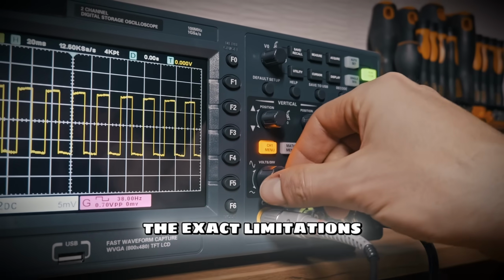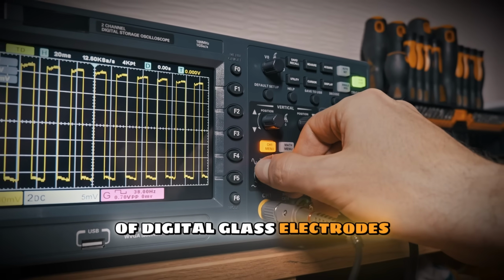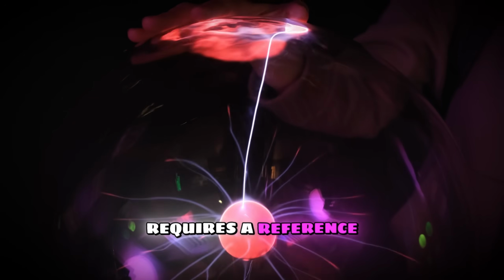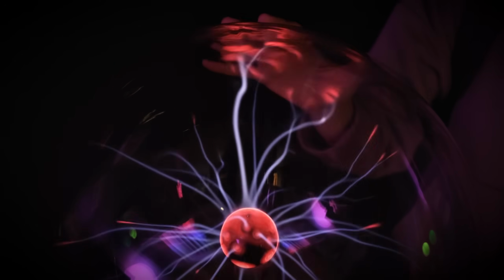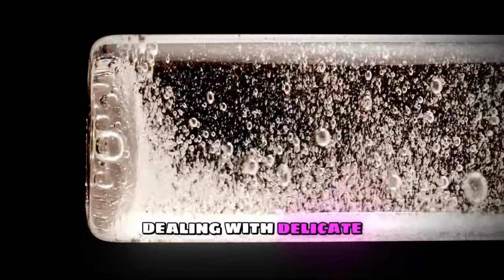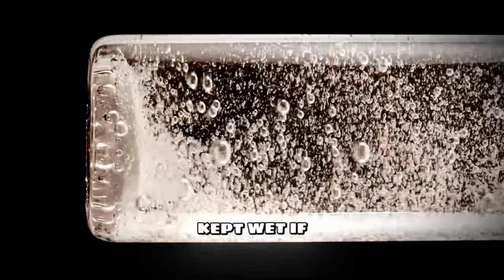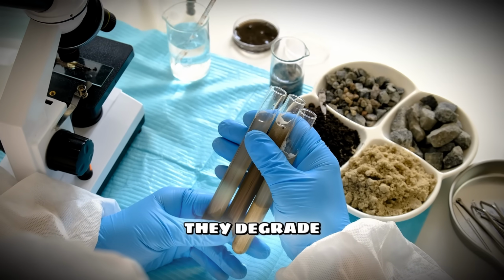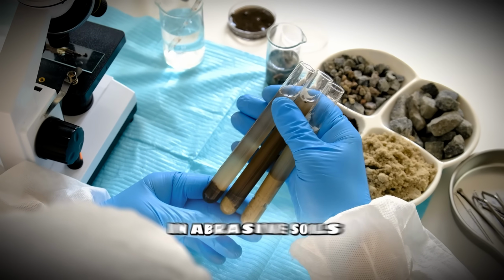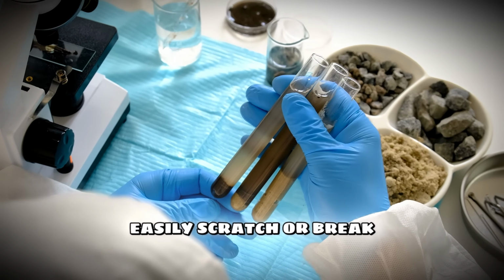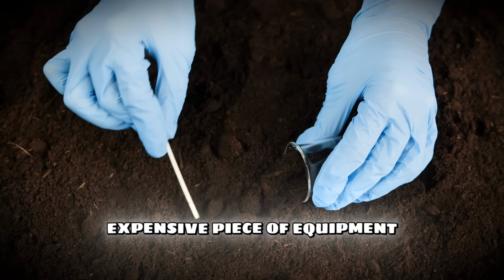Let's talk about the exact limitations of digital glass electrodes. A glass electrode requires a reference liquid to complete its circuit. This means you are constantly dealing with delicate glass membranes that must be kept wet. If they dry out, they degrade. If you test in abrasive soils, the glass can easily scratch or break, instantly ruining an expensive piece of equipment.